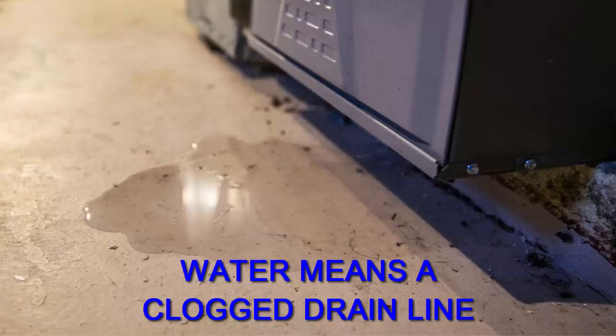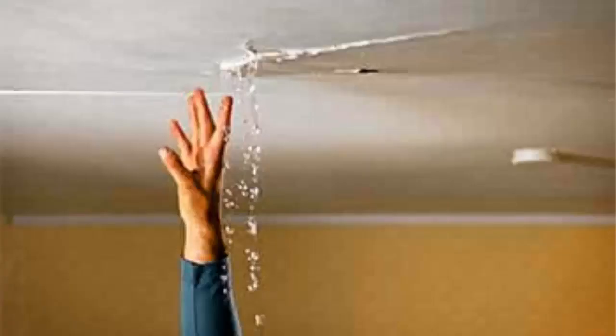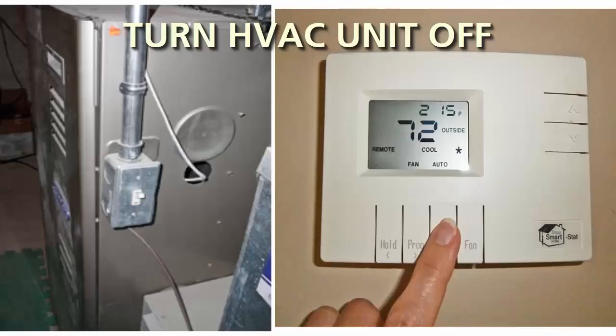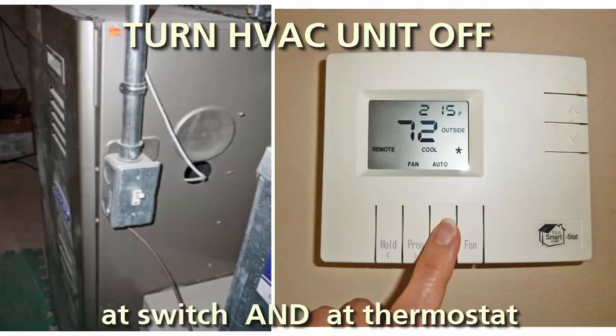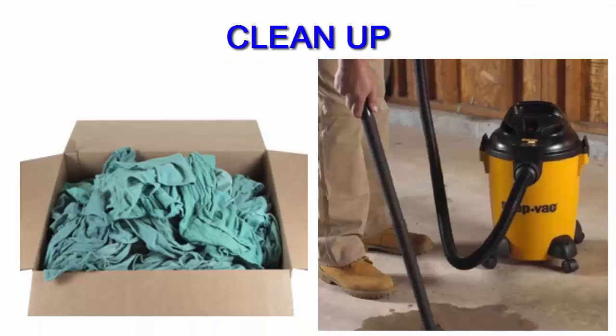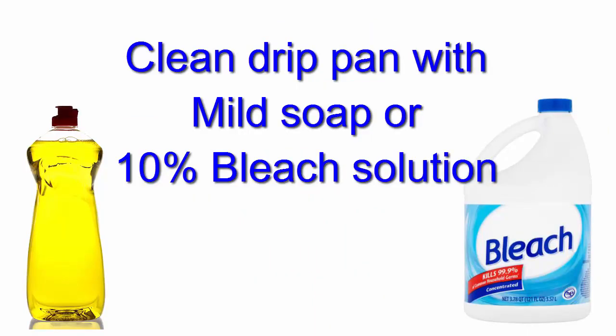If your HVAC unit is in the attic, you might see water coming through the ceiling. If you find such a leak, turn the HVAC unit off at the electrical switch and at the thermostat. Using rags or a wet-dry vacuum, remove all the water from the drip pan and around the unit. Then clean the pan with a mild dish soap or 10% bleach solution.